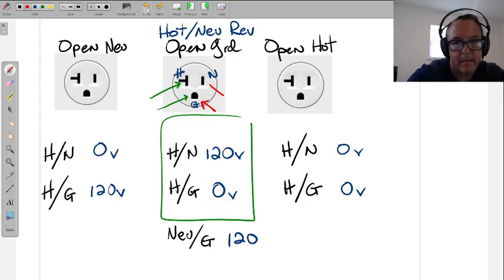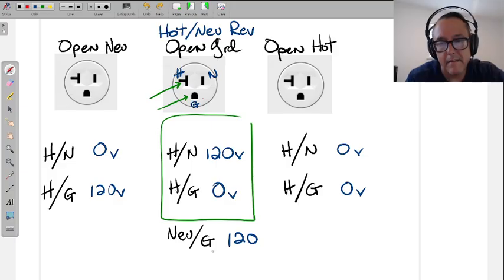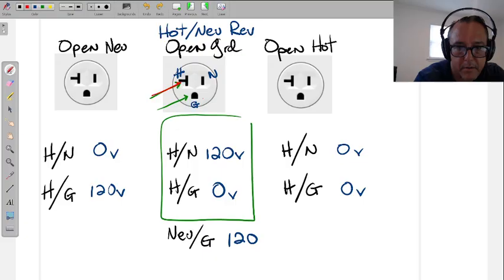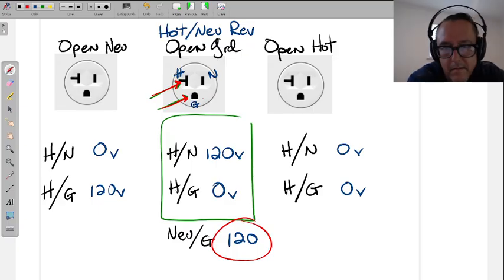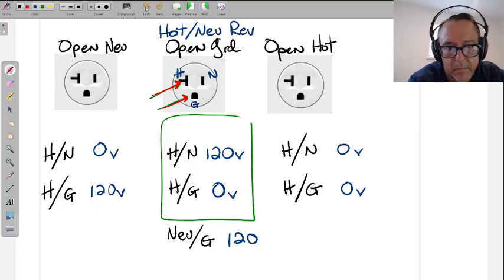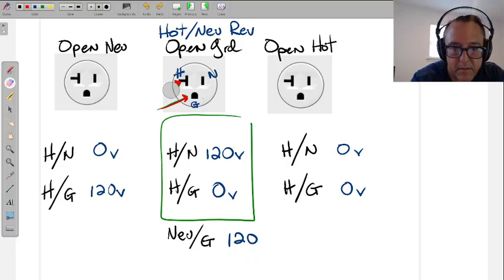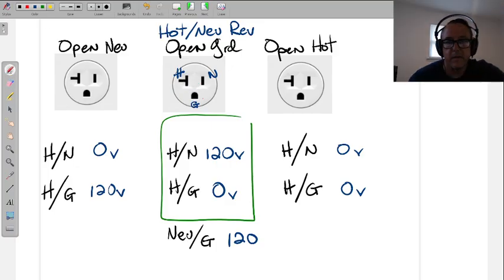Can't happen. But I do the third test now, and the third test is, as you said, between the neutral and the ground. And now, wild, it's going to give me 120, which should never, ever, ever be the case. The neutral and the ground should have 0 on it. And so that's what we determine now.